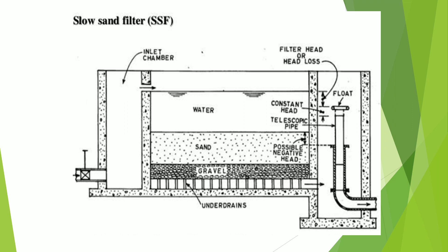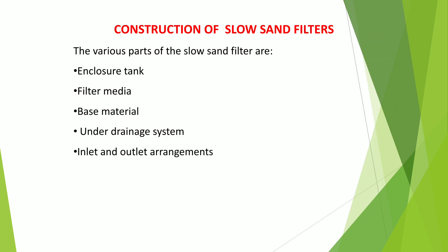The filtration rate is very small. In the schematic diagram, you can see at the left side the inlet chamber, and at the right side some pipes which are used and the head to be maintained. Water is at the top, then sand at some depth, gravel at the bottom, and under-drains are provided at the base to collect the filtered water and supply it to further water treatment processes.